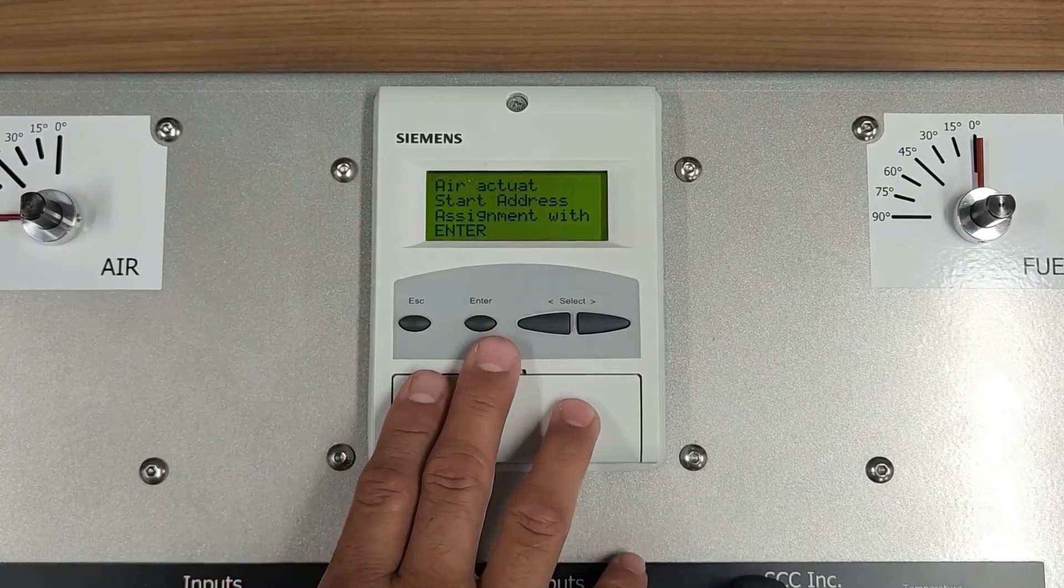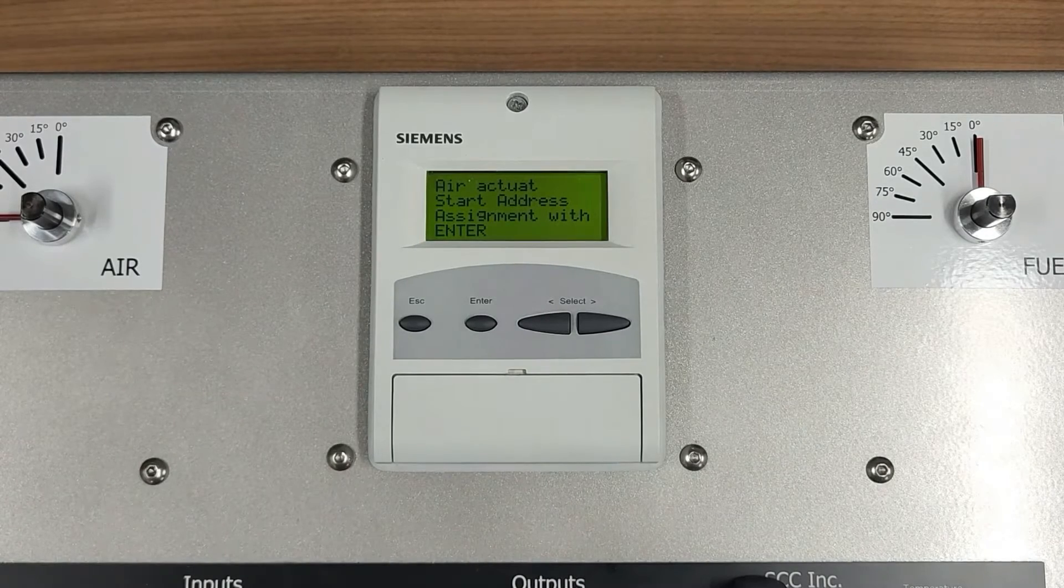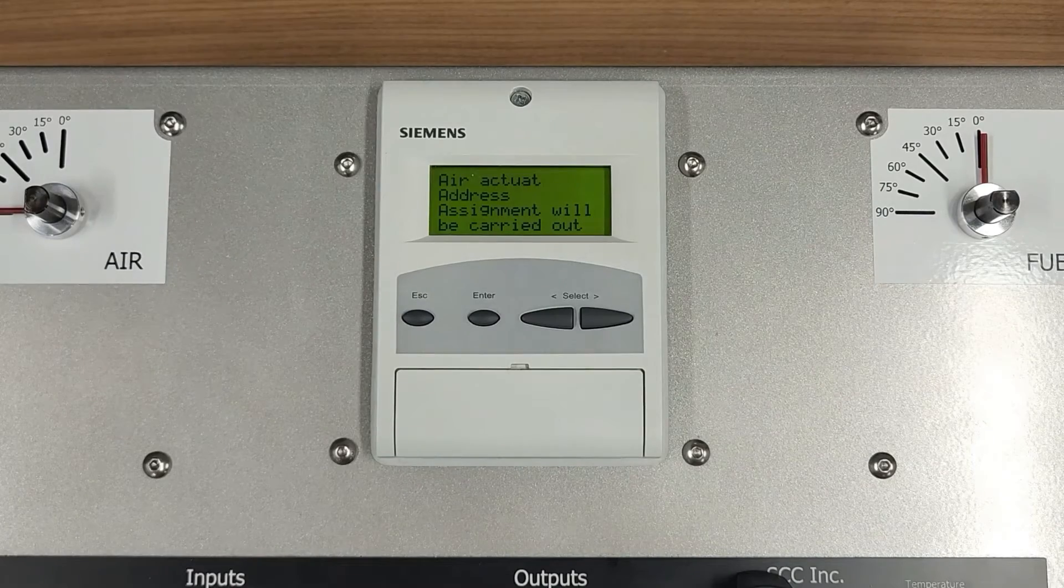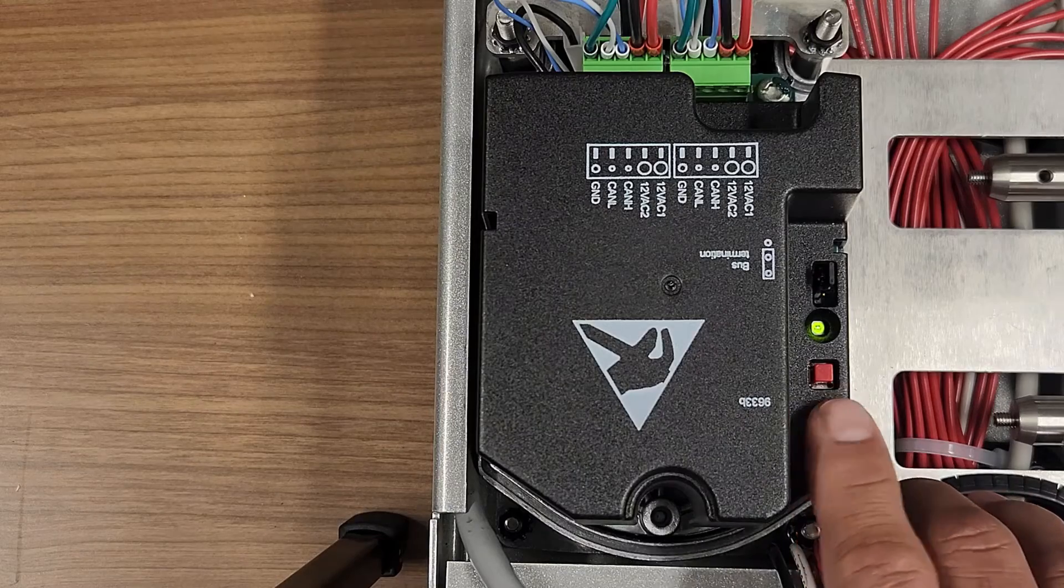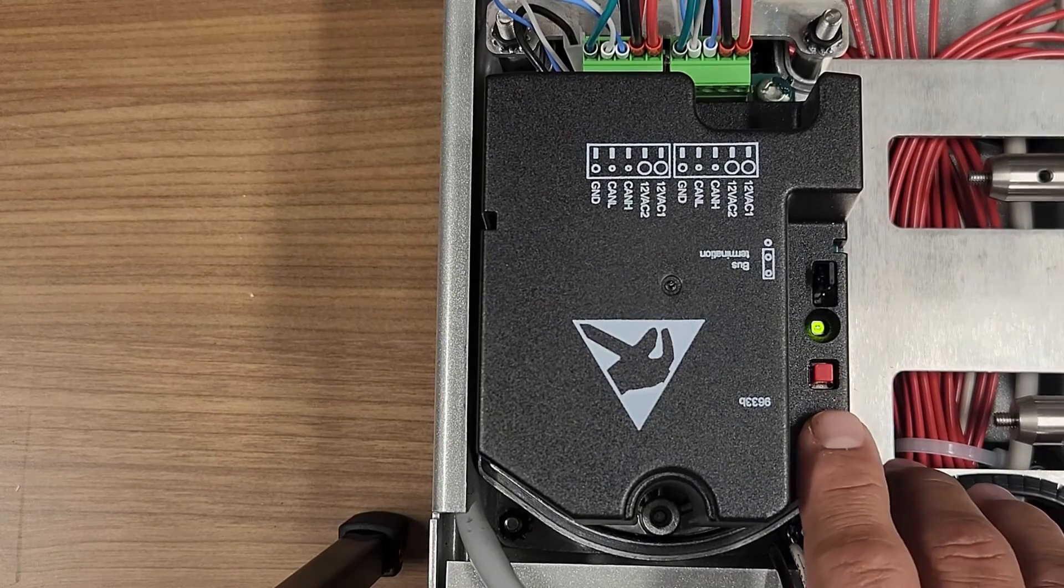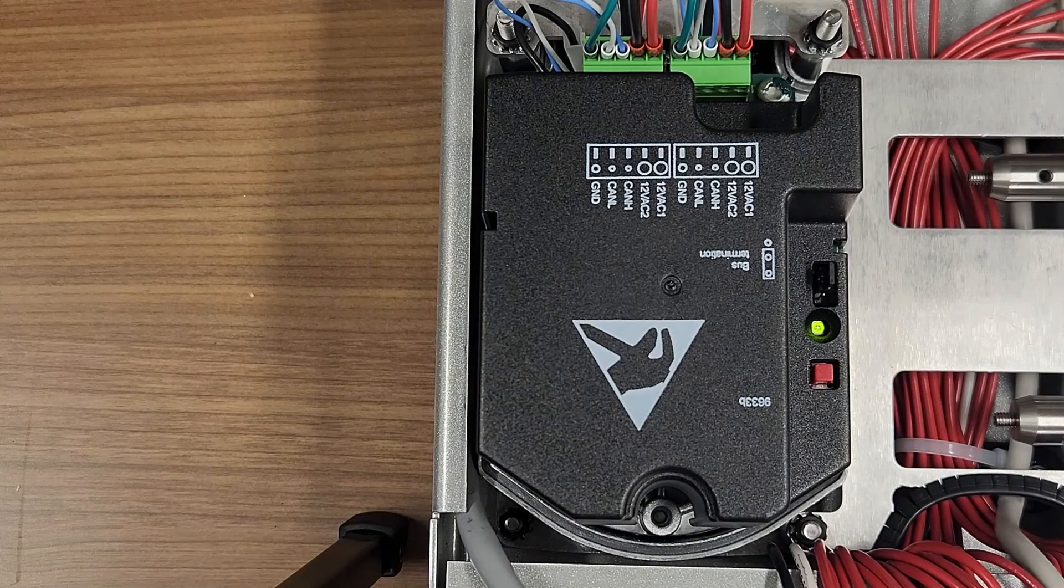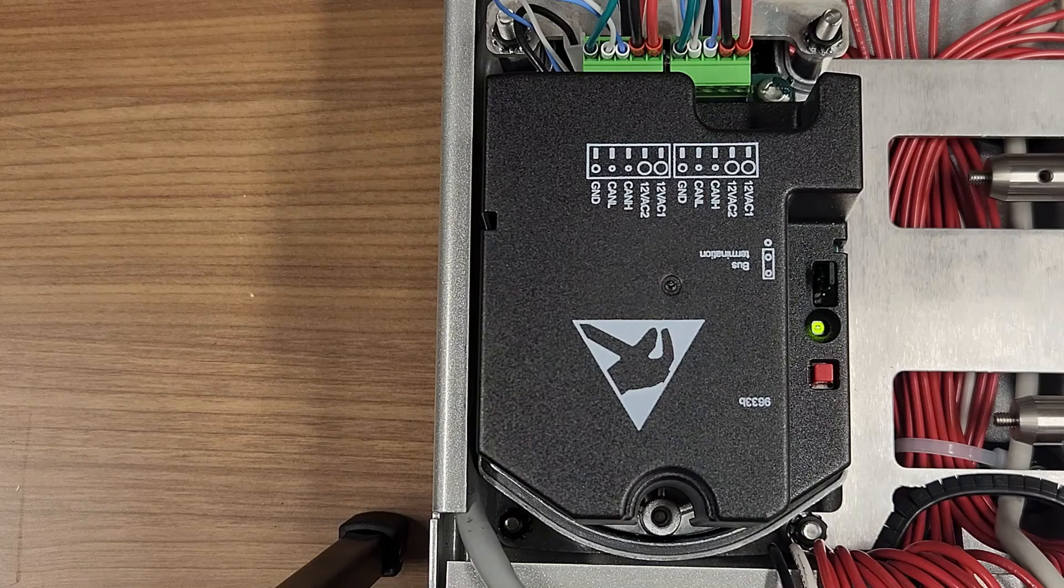And the display will serve as a guide through the rest of the configuration. Press Enter. And the display will direct you to press the red button on the selected actuator. This red button is located on the back of the actuator under the cover. In this example, we have already removed the back cover. But, in order to do this, you will be loosening the three Phillip head screws on the back cover.